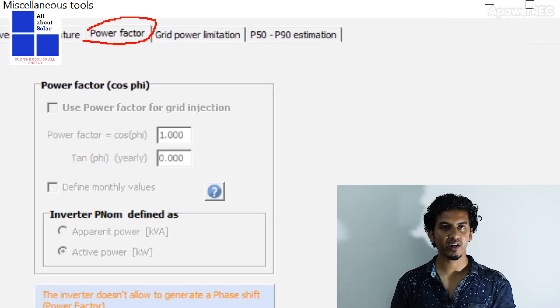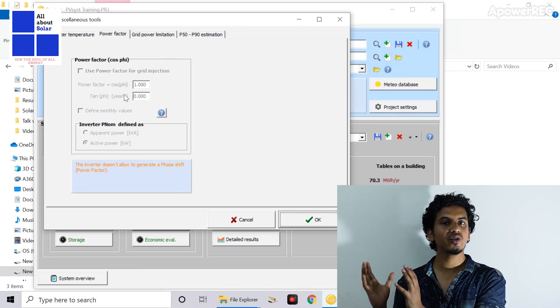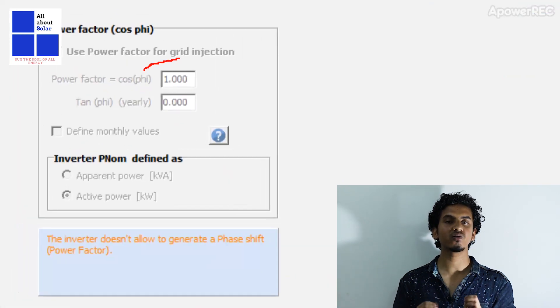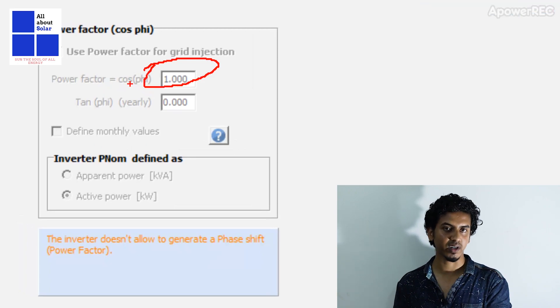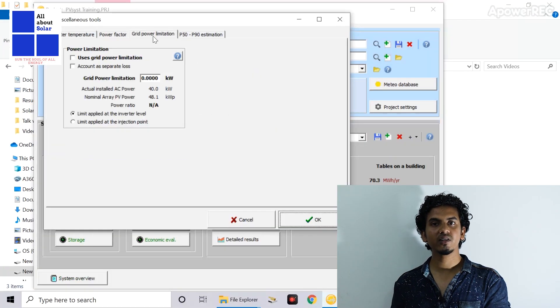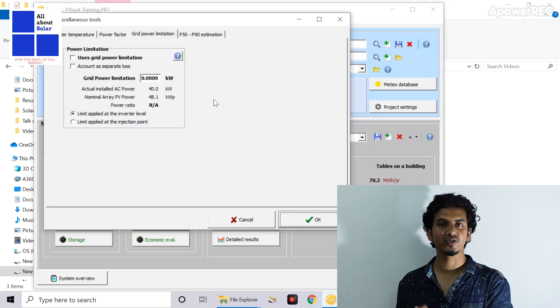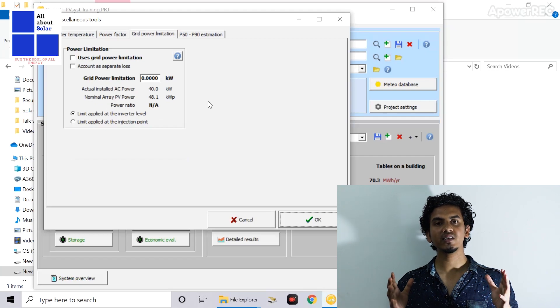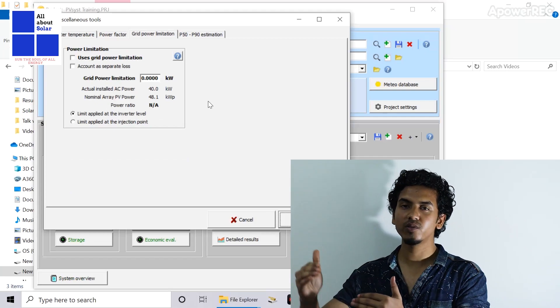The next point is the power factor. Generally, on-grid solar inverters have unity power factor, so there is no need to change it. The third one is power limitation. This is basically required where you need to provide any kind of capping of power — for example, in India the net metering system cap is 1 megawatt, meaning beyond a 1 megawatt plant you cannot inject power to the grid.